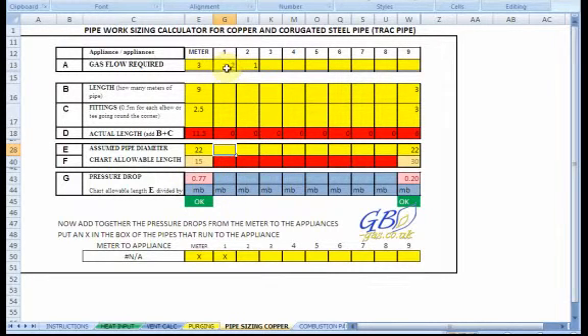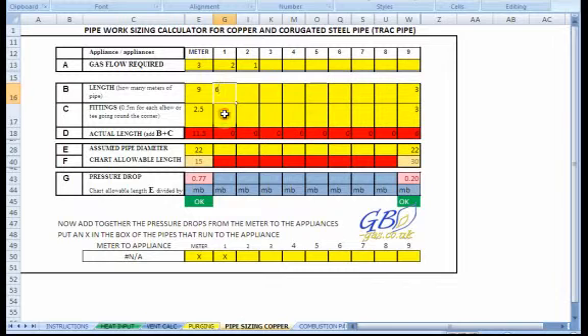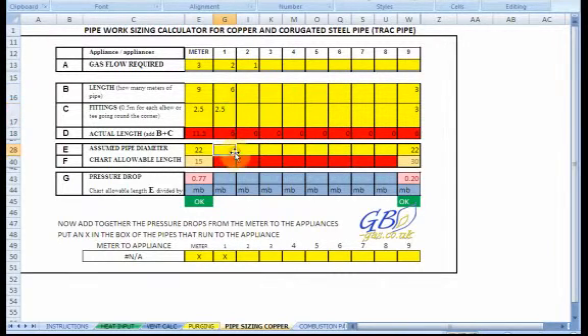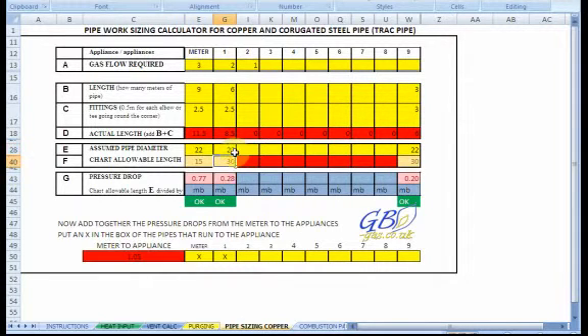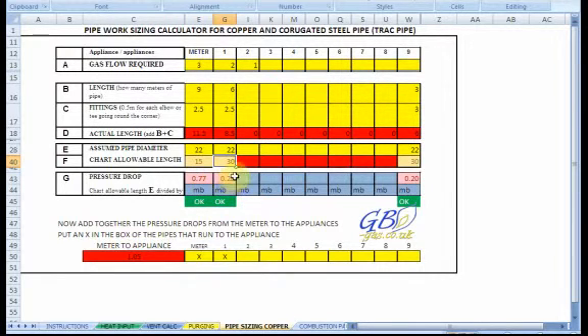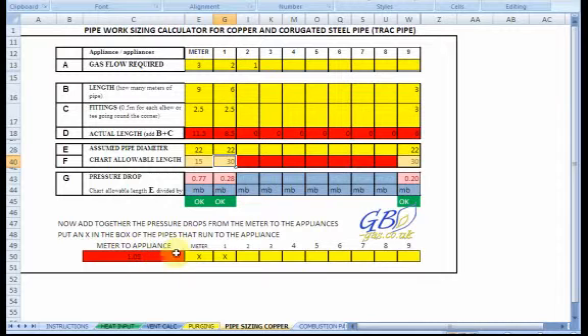We then go on to stage two. So, for this appliance, for argument to say, it's going to a boiler, and I have got six metres of pipe going to the boiler, with five elbows again. So, we'll just put in 2.5. And I'm going to assume I'm taking 22 to the boiler. Now, straight away, you can see there, I've got 0.77 coming up to the tee piece, and then another 0.28. Now, if I add those two together, which I put the crosses in here, I get 1.05. That's a bit too much.